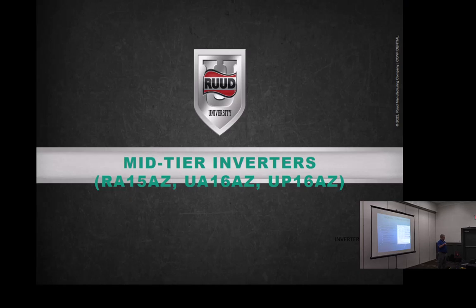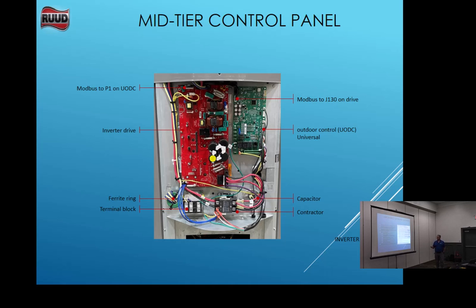This is our mid-tier controller panel here. This is a Regal drive, a big bright red thing here that Regal makes for our mid-tier units. You will see some changes. This is inverter driven, up to 70%. If it doesn't maintain temperature up to that amount, we go to a contactor, and capacitor, and line voltage.